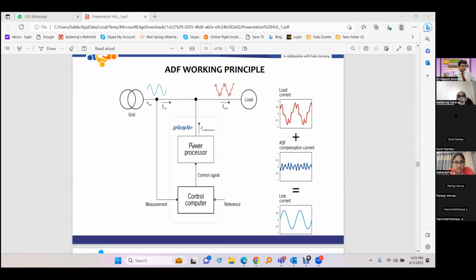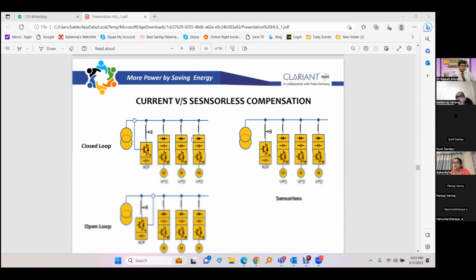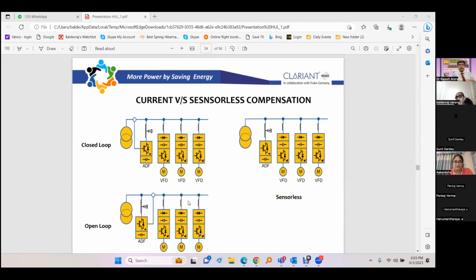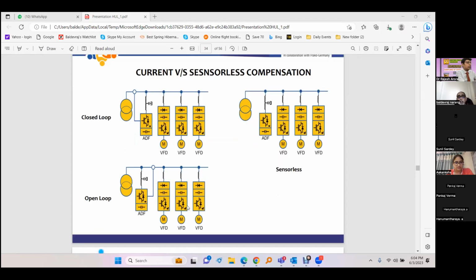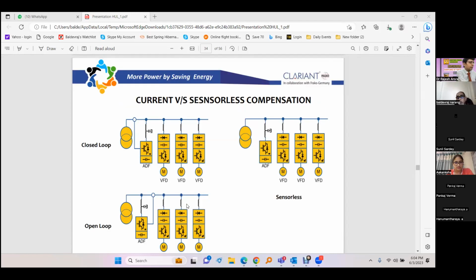With the active filter, we can have even voltage harmonic correction; the background correction is also possible. Here we have a sensorless control and we can even control the voltage harmonics. But not everybody is doing it, only some manufacturers have this facility available.